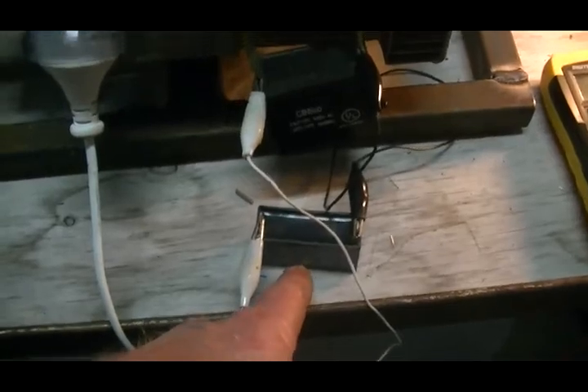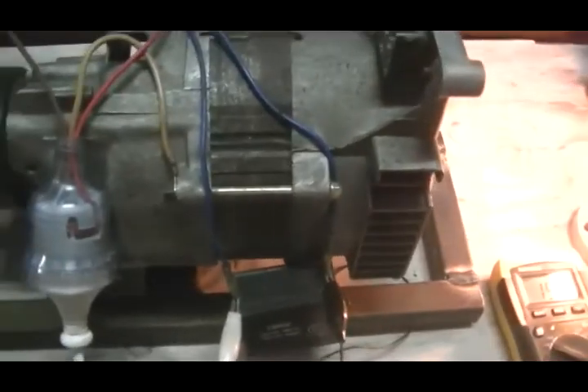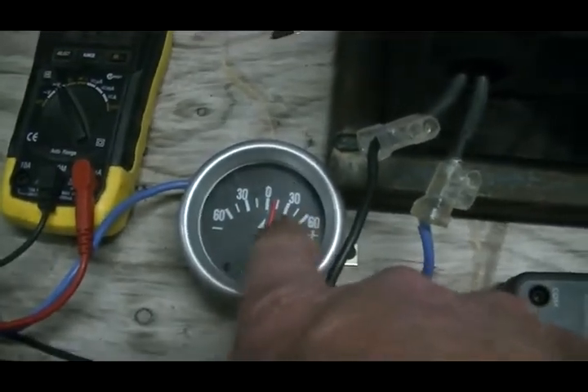Now if I put our small cap back on, remove the large cap, and have it running in standard trim as it was from factory, these amps pull up just over 15 amps.